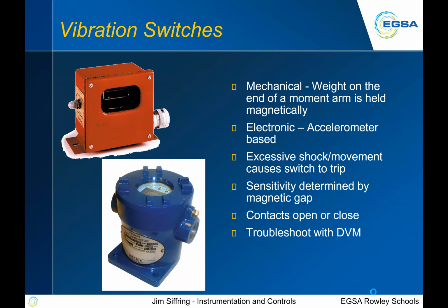So, vibration switch: you see the red device in the upper left. That was the old standard Murphy shock switch, is what we call them. And really all it is, is a contact that's held together with a magnet, and you can adjust the sensitivity, or the amount of pull that magnet has on that arm. They went into things like rental sets, rental generators, rental compressors. If the device took a shock, say it got dropped off a crane or a truck as it's being moved from someplace to another, or got into an accident, it would break that connection. Then the rental company could tell that something had happened.